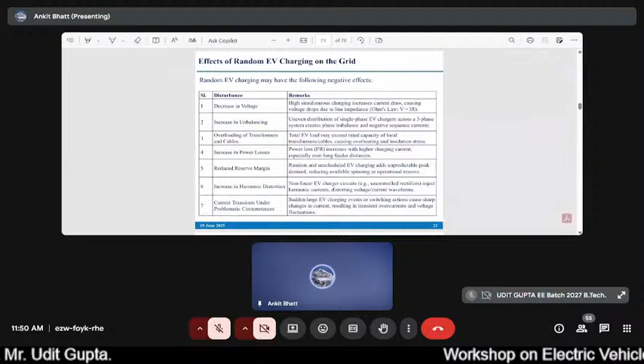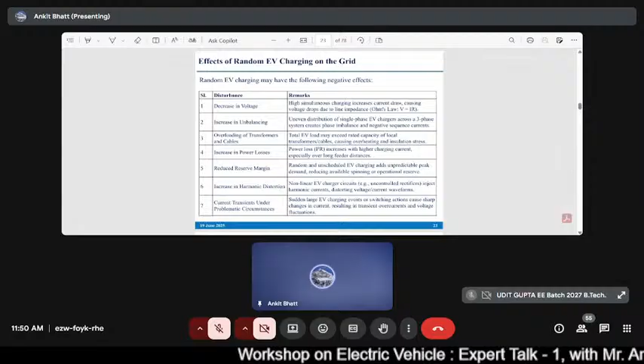Suppose in one phase one EV is charging, in the second phase no EV is charging, and in the third phase three EVs are charging. This can cause unbalancing, overloading of transformers and cables, and increase power losses because as more charging current is drawn, the I-squared-R losses increase over long feeder distances. It will reduce the reserve margin that the grid has, so if any unpredictable peak comes, the grid may not be able to handle it. It will also increase harmonic distortion, as charger circuits inject certain harmonic currents during different phases of their charging. These are some of the issues that can emerge when random EV charging happens on the grid.